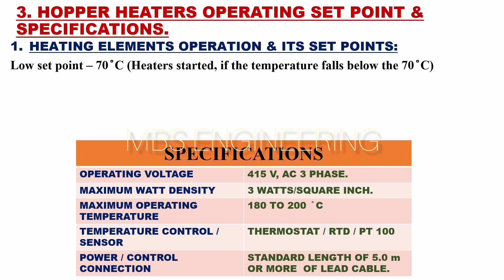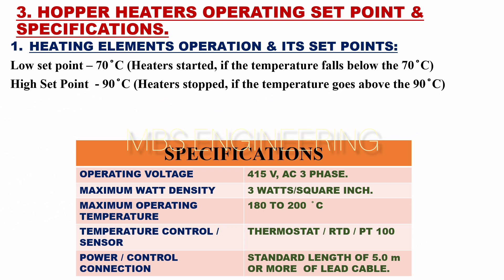We learn about the hopper heater's operating set points and specifications. Regarding the hopper heating element's operation set points: the low set point is 70°C, meaning heaters start if the temperature falls below 70°C. The high set point is 90°C, meaning heaters stop if the temperature goes above 90°C. The above set points can be adjusted based on the operating conditions.